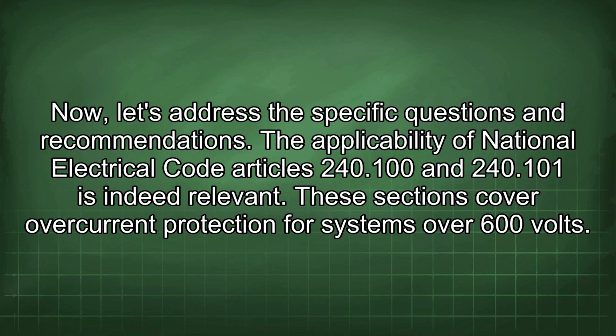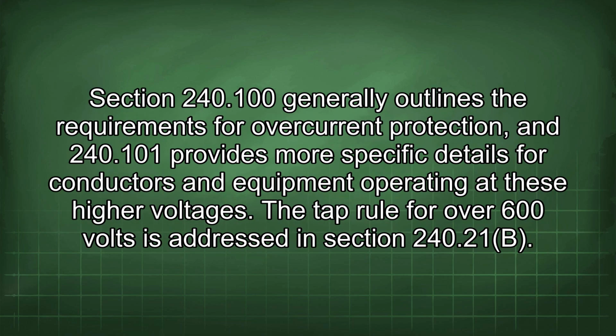The applicability of National Electrical Code Articles 240.100 and 240.101 is indeed relevant. These sections cover overcurrent protection for systems over 600 volts. Section 240.100 generally outlines the requirements for overcurrent protection, and 240.101 provides more specific details for conductors and equipment operating at these higher voltages. The tap rule for over 600 volts is addressed in Section 240.21(B).